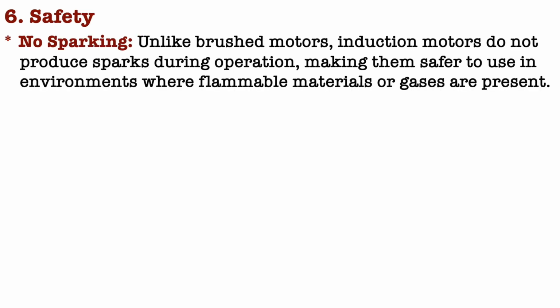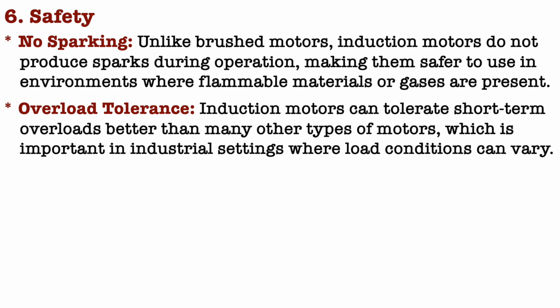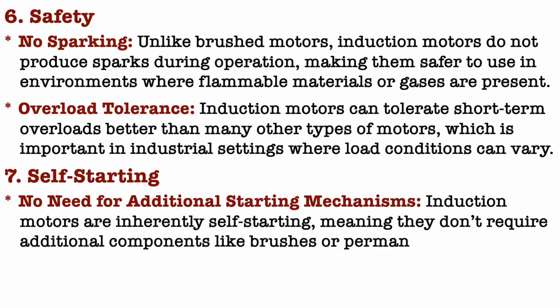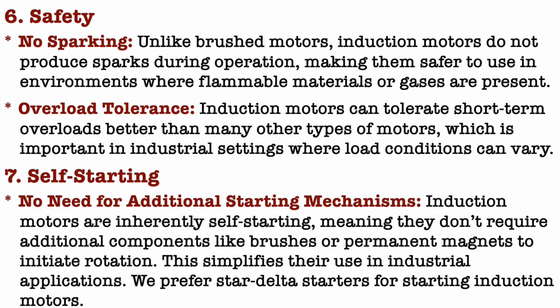Next is safety. Unlike brushed motors, induction motors do not produce a spark during operation, making them safer to use in environments where flammable materials or gases are present. Overload tolerance: induction motors can tolerate short-term overloads better than many other types of motors, which is important in industrial settings where load conditions can vary. Next is self-starting. Induction motors are inherently self-starting, meaning they don't require additional components like brushes or permanent magnets to initiate rotation. This simplifies their use in industrial applications.